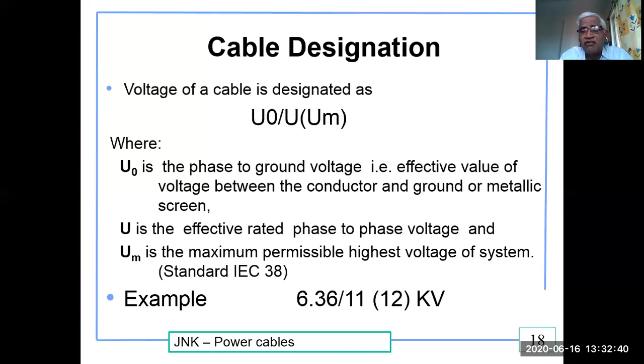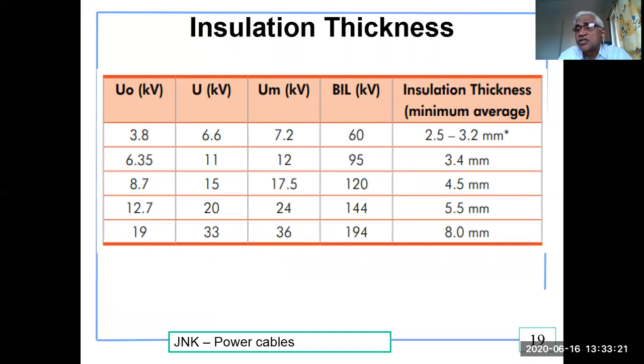As you go down there, you have 3.8 kV, which is equal to 6.6 kV line to line. The next ones are the 11 kV cable, 15 kV, 20, and 33, whereas the Um will be equivalent to that. Now the insulation you can see goes from 2.5 to 3.2 millimeters for the first one, and you keep increasing the thickness of the cable as the voltage is increasing, because kV per mm is to be considered in these cases, right?